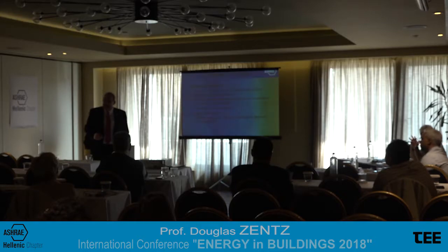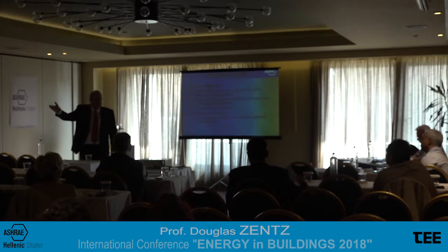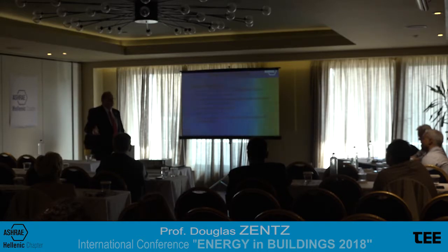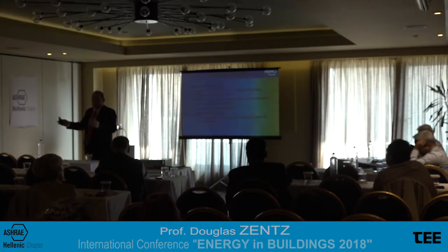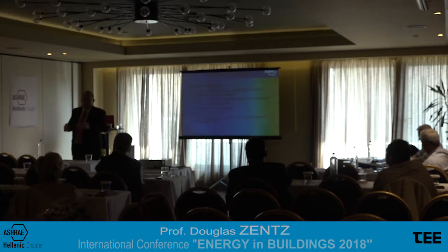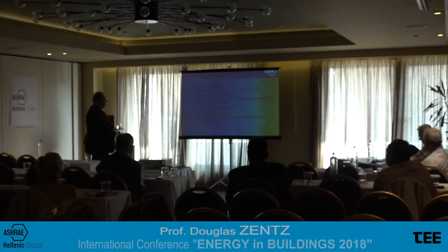They also want you to do what's called peak load reduction. And they make a flat statement. They want you to reduce your load by X%. It's up to you how you do it. For those of you that saw the presentation earlier about load shift, well, that's one way you could do it. There are other ways, maybe widening your dead bands and illustrating through modeling that by widening your dead bands, you're reducing your peak load. However you do it, it's up to you. But they want you to do it. And then there are many other areas which are much more stringent than 90.1.